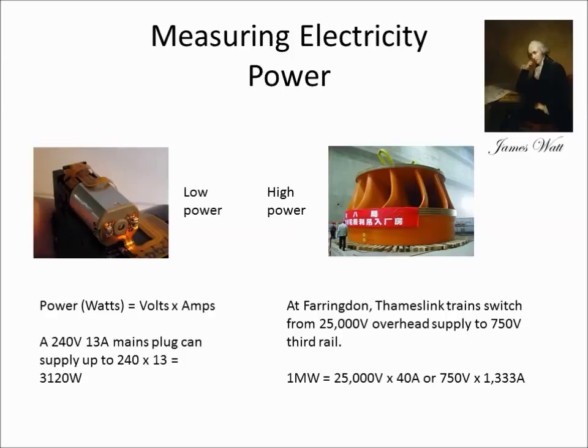Those overhead cables are safely out of the way, beyond reach, so we can safely put 25,000 volts on them. On the south, we've got the third rail down by the track along the running rails. If you put 25,000 volts on that, it would probably spark to the ground and be extremely dangerous for any track workers. So those actually run at just 750 volts.